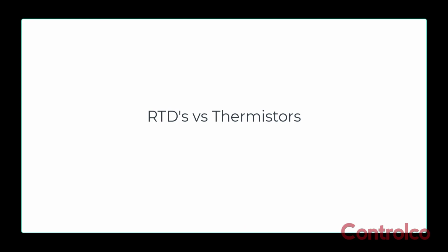Another big thing might be cost. Typically, an RTD is more expensive than a thermistor. So in our typical HVAC application where we have 200 VAV boxes, saving $10 a sensor might come into play in the overall scheme of things. So just some things to think about.